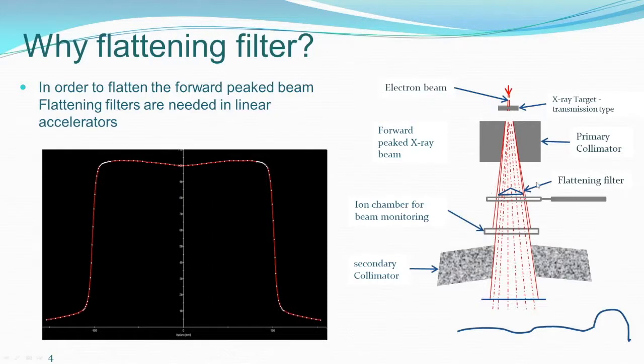The flattening filter was introduced between the target and the chamber, and the resultant beam profile became a flat beam profile. You could ask me, it is not strictly flat. You see a dip at the middle, which means the central axis dose is lower than the off-axis dose. This we refer to as the horns. The reason is that one flattening filter is used for one particular energy and made for certain reference field sizes. When you go to other field sizes, it may not make it exactly flat, and you tend to get a dip at the middle, which is referred to as the horns at the off-axis regions.